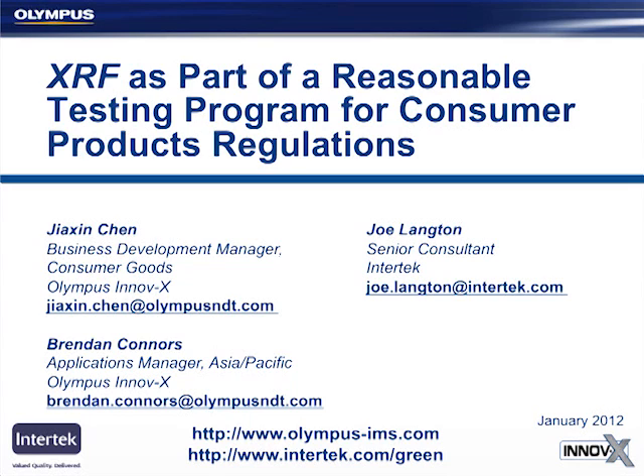We don't see isotope sources being used as much for consumer products applications. A lot of that has to do with the regulatory requirements where manufacturing is going on in so many different countries, and in a lot of places the requirements are more stringent. As far as performance difference between those, with a tube-based instrument, an isotope source is always running at one particular energy, and an X-ray tube has a maximum energy, but it's adjustable over a whole range. So that in most applications can give you better sensitivity over a whole range of elements.